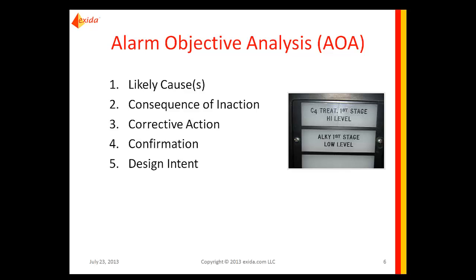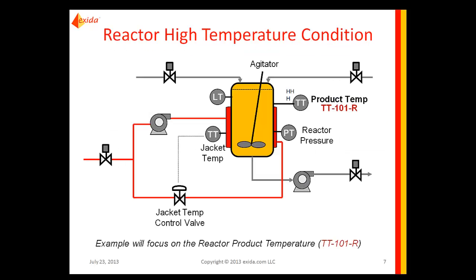Alarm Objective Analysis includes discussion of the following: what scenarios could trigger or cause the alarm; the potential consequences if the operator does not respond; the corrective actions that should be taken by the operator to prevent the consequences; the method for confirming that the alarm is real; and the purpose or design intent. It focuses on confirming that alarms are legitimate and meaningful, making it very effective at identifying unnecessary alarms and helping define only the minimum set of alarms needed to keep the process safe and within normal operating limits.